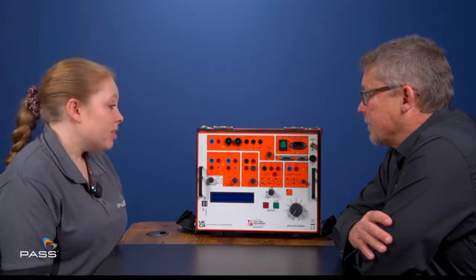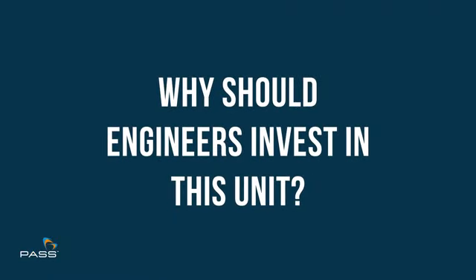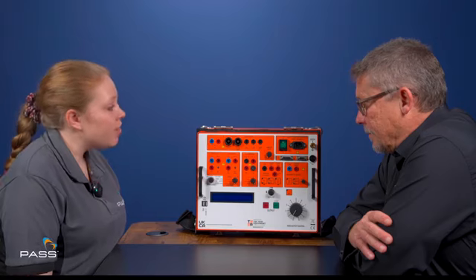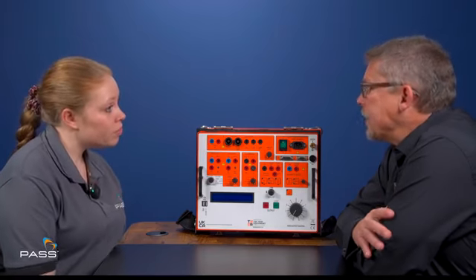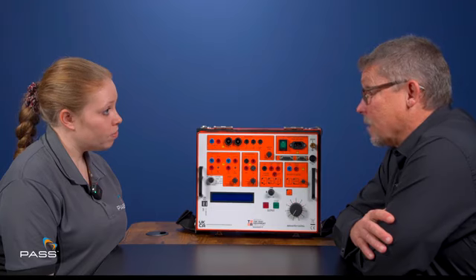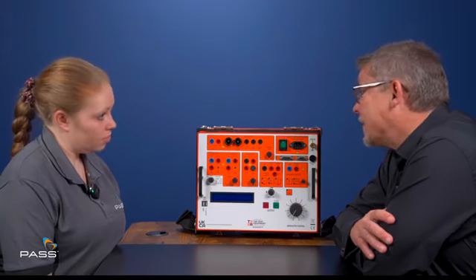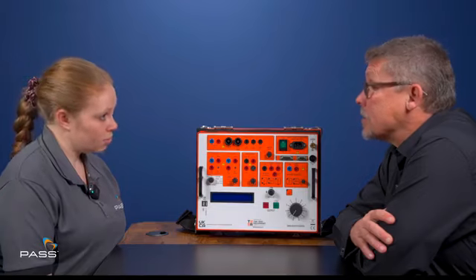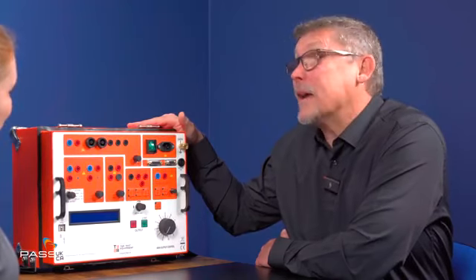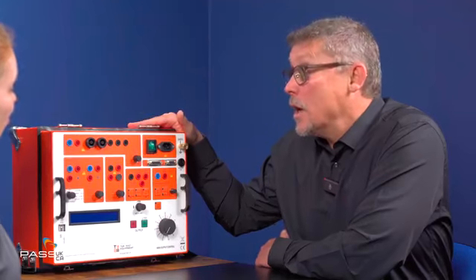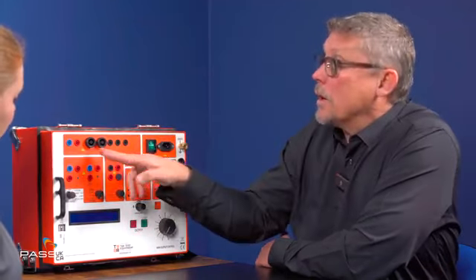So there are many secondary current injection testers on the market. Why should commissioning engineers or maintenance engineers invest in this one? Well, Jess, you're right. There are many. I mean, if you look at T&R alone, we've probably got 5 variants of secondary current injection test sets. This I would describe as our flagship, and dare I suggest probably the flagship amongst secondary current injection test sets. The reasons being very simple. Number one, not many will give you 200 amps at 10 volts. Most of them top out around about 100 amps.